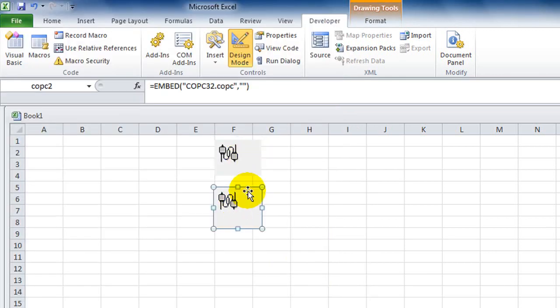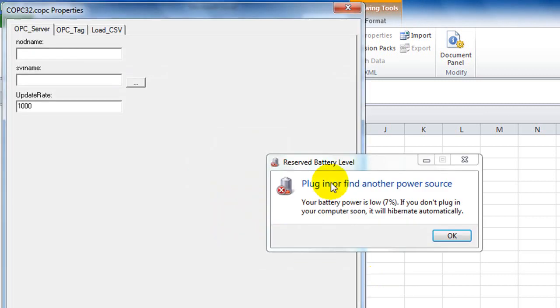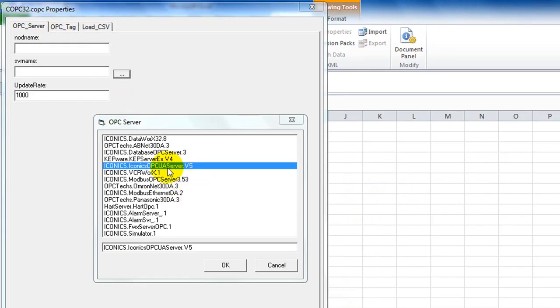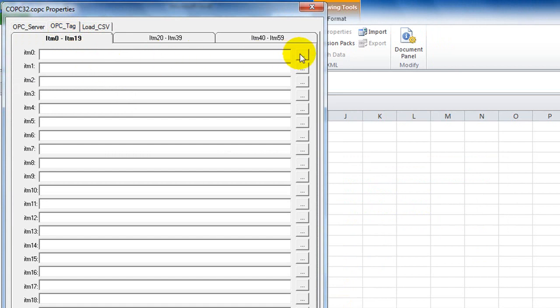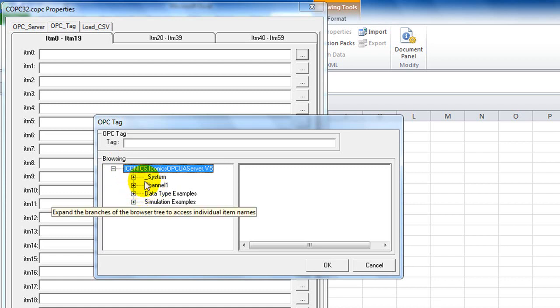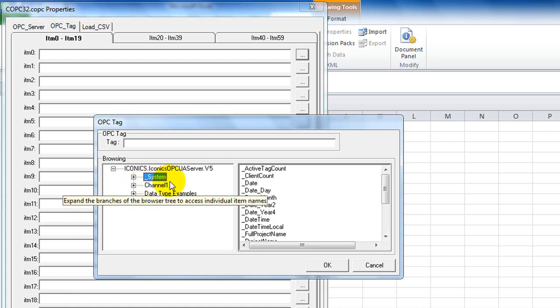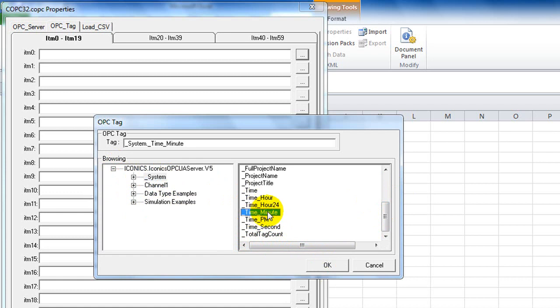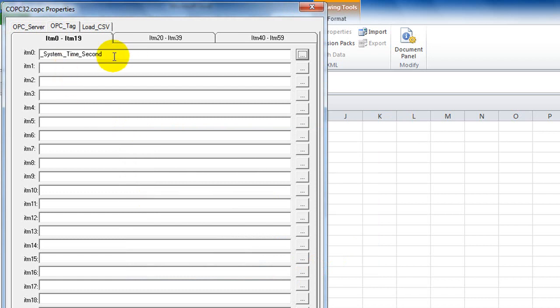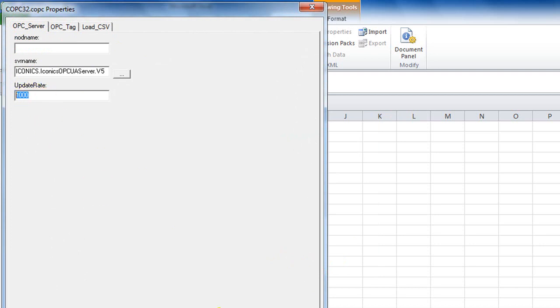Click OK. For the second control, I'll also connect to the same OPC server, but choose a different OPC tag — I'll select a tag from the System branch and choose Time Second. This OPC tag changes every second. If you want a tag that changes every minute, you can use Time Minute. I'll use this tag as a timer since it changes every second. Set the update rate to one second and click OK.